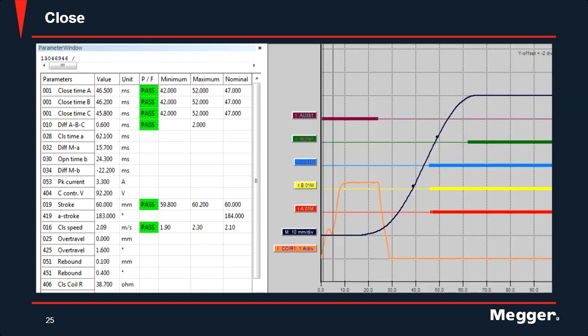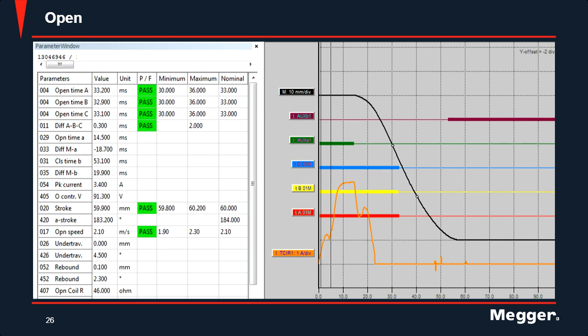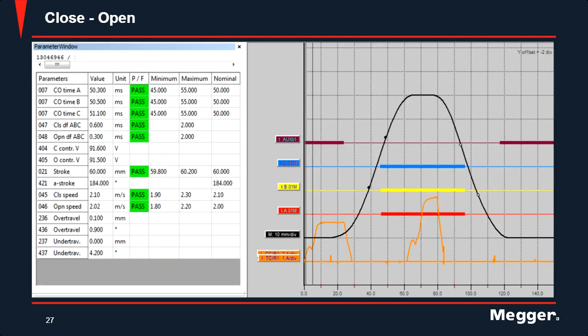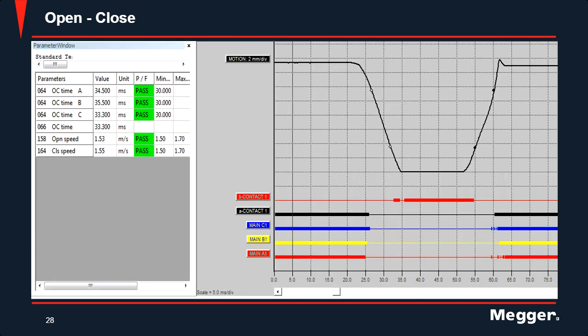So here's a few different little traces from all five operations that I discussed. This is an example of a close operation. If you look here, the black line is your travel. And there are little black dots on each one. Those are your speed calculation points. Your red, blue, white, blue, yellow, and red are your timing traces, your timings. The thin line is an open, and the thick line is your close. This is a representation of open. As you can see, the travel curve is going in the opposite direction. You have thick lines for close, and then it comes to your opening operation. This is the close open operation. As you can see, it goes open, it closes, and then reopens. And the same thing with an open close and the open close open.